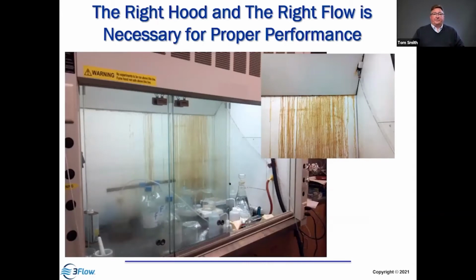Now, another type of hood system is equipped with a variable air volume system. When you close the sash, it reduces the flow. But they were working with acids and generating large quantities of material. As it went out through the ductwork, that minimum flow wasn't sufficient to remove it from the hood, and it rained back into the hood. You could see it dripping down the back panels inside the hood. So that indicates it's just not sufficient to provide containment and removal of the materials from the hood. So we have to look at the right flow.